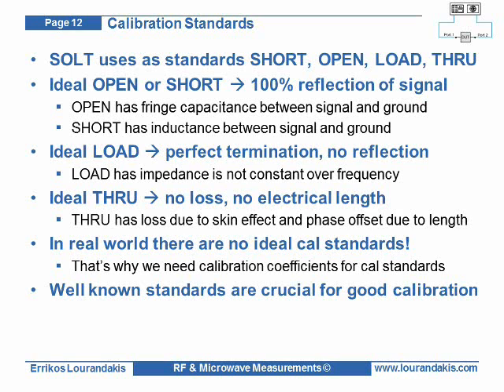Calibration standards play a crucial role in network analyzer measurements. A widely used calibration routine is called SOLT, named from the standards: short, open, load, through. An ideal open or short would have perfect signal reflection. In reality, the open has a parasitic fringe capacitance between signal and ground, and the short has an inductance between the two terminals. An ideal load would be a perfect termination resulting in zero reflection, but real-world load standards have a frequency-dependent impedance. An ideal through would have zero loss and electrical length, but in reality a through standard has some insertion loss and phase shift. In short, there are no ideal calibration standards, which is why we need well-defined standards for a quality calibration.